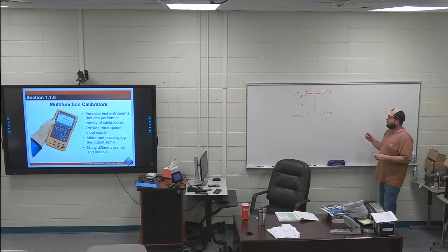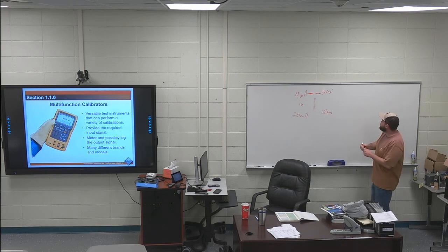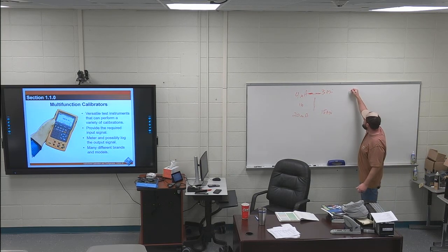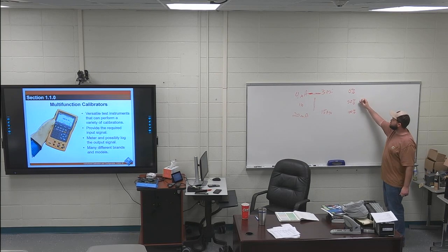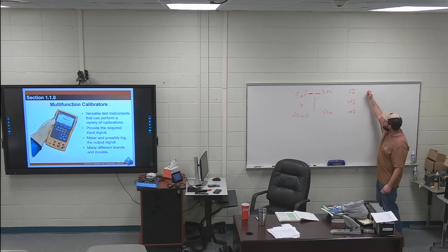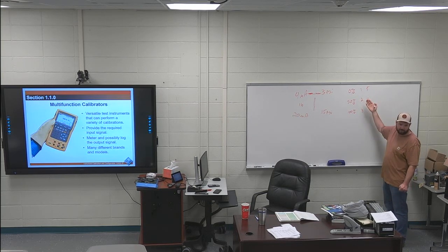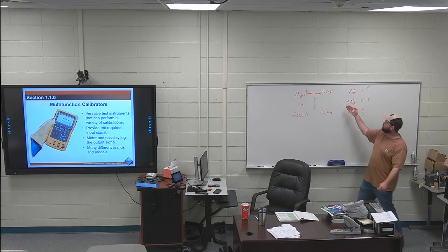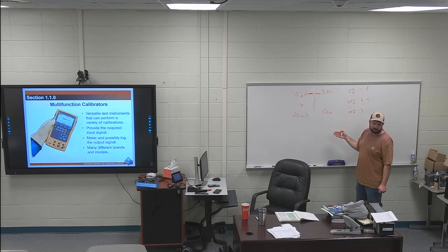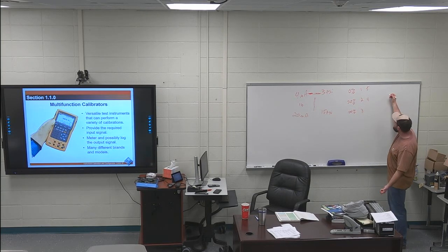While I say 3 and 5, it's 3 different points. A 3-point calibration would be 0%, 50%, 100%. But you don't just do 1, 2, 3. You actually go 1, 2, 3, 4, 5. You go all the way up and back down. A 3-point calibration is more accurate than a zero and span because you're doing something in the middle. You also have a 5-point calibration.